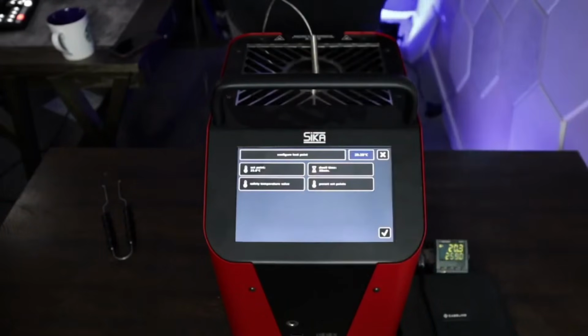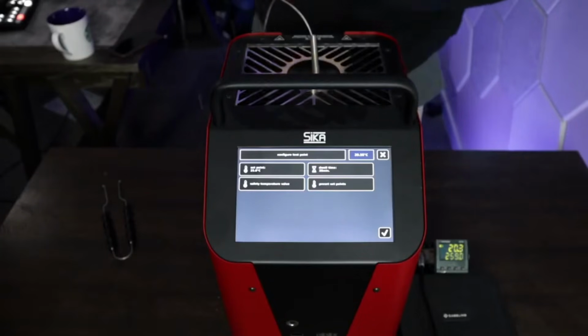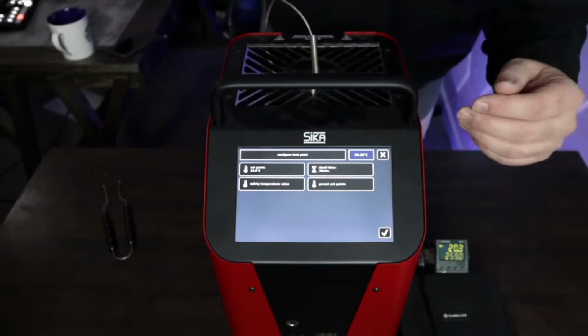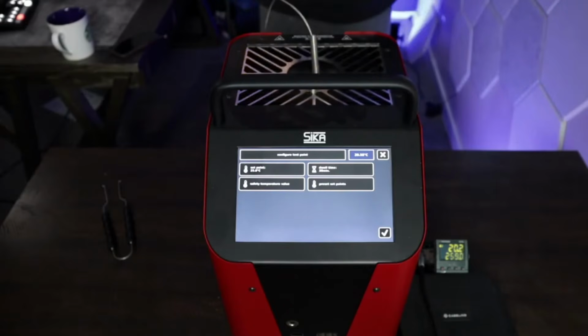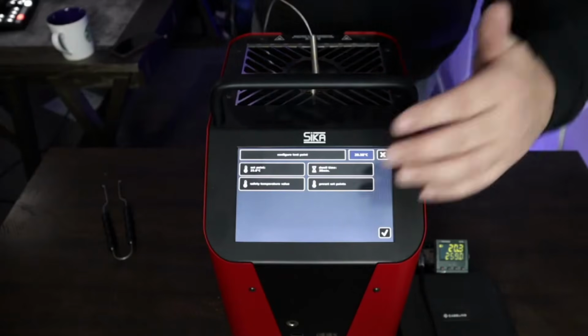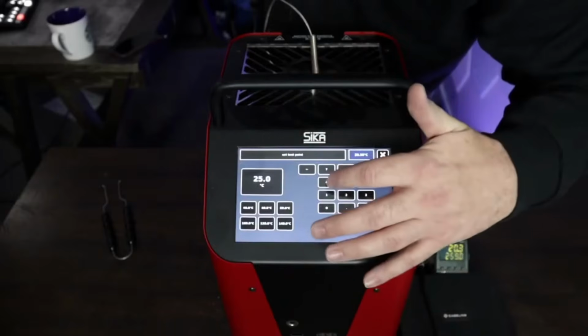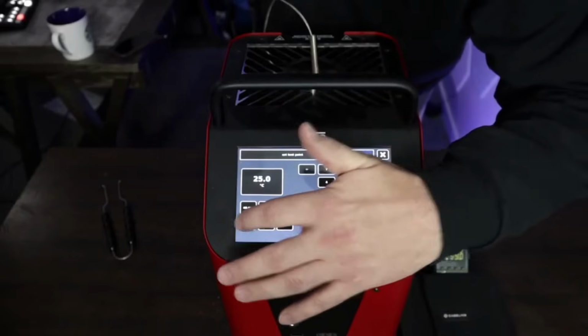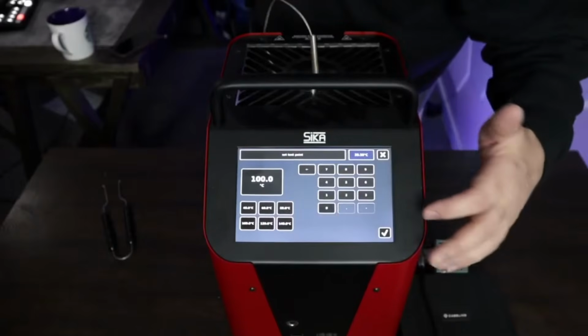So when you're using a dry well and you're on site, typically a customer is going to say, hey, I want this tested at this point, this point, this point, or they could leave it up to you and you ask them what ranges they usually use. In this case, I'll just say, hey, we're going to test this at 100. What's nice is they have little buttons here where I can just put it in upside down.